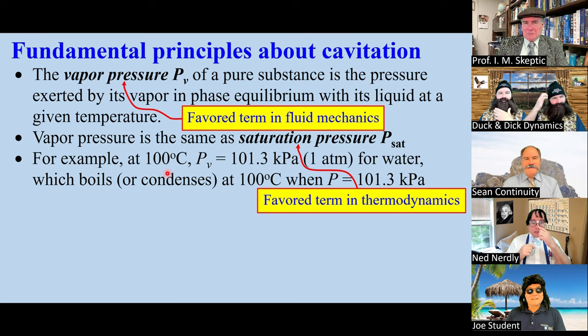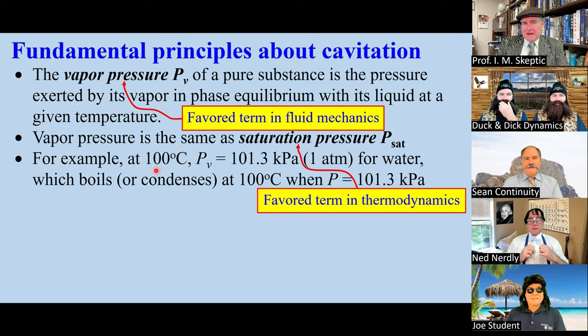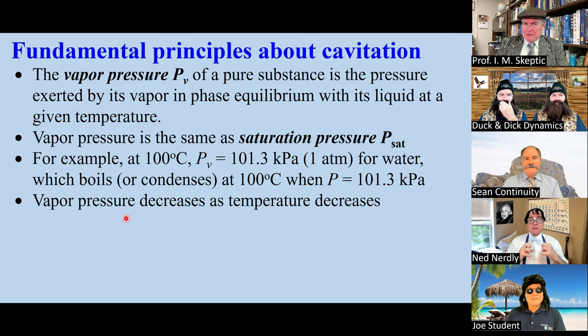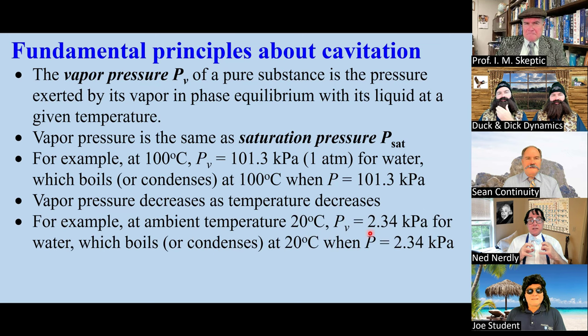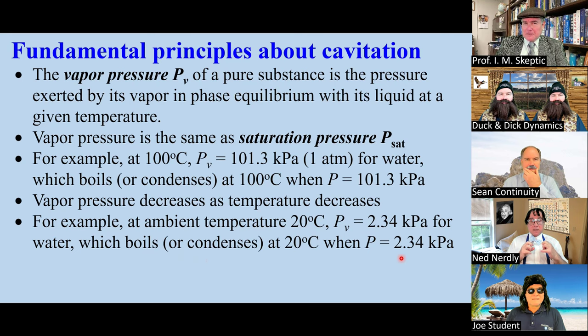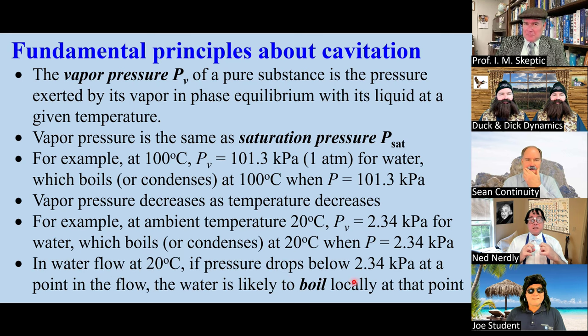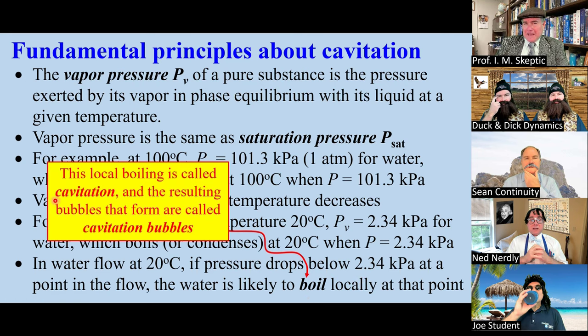We all know that water boils at 100 degrees C at 1 atmosphere — that means PV is 101.3 kPa at 100 degrees C. But vapor pressure decreases as temperature decreases. At 20 degrees C, PV is only 2.34 kPa. So water will boil or condense at room temperature when the pressure is this low. If the pressure drops below PV at any point in the flow, the water is likely to boil locally. We call this cavitation.